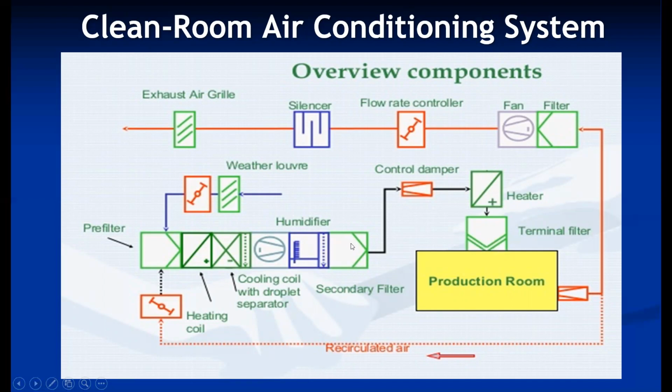Because filtering all the air also causes a pressure drop, and that increases the pumping power as well. So the general level of filtration happens in the air handling unit, and some special-level filtration is done where required, operation to operation.